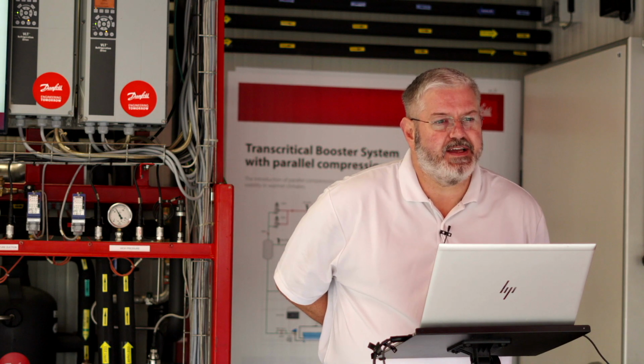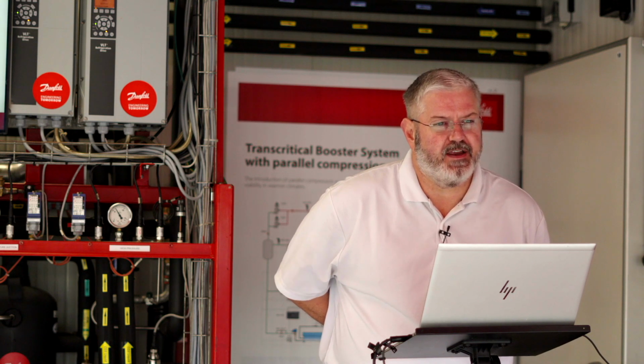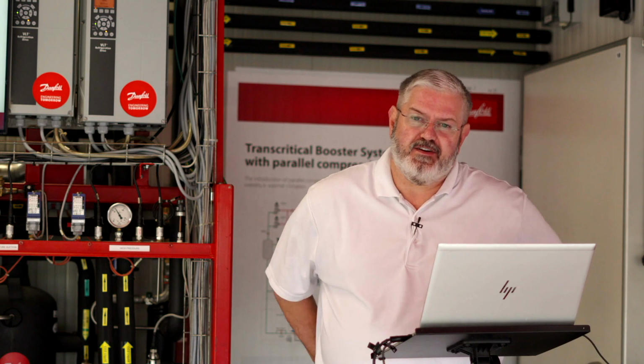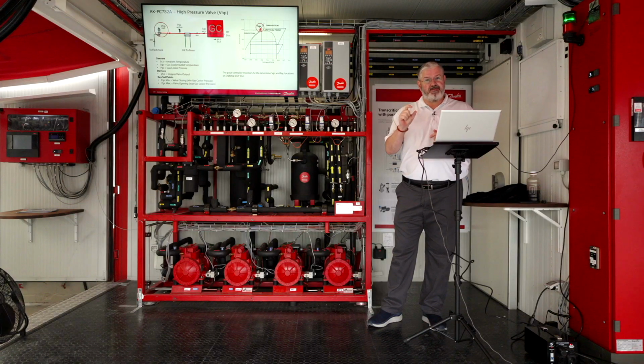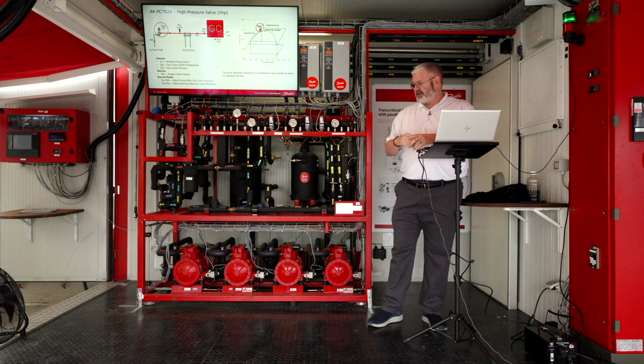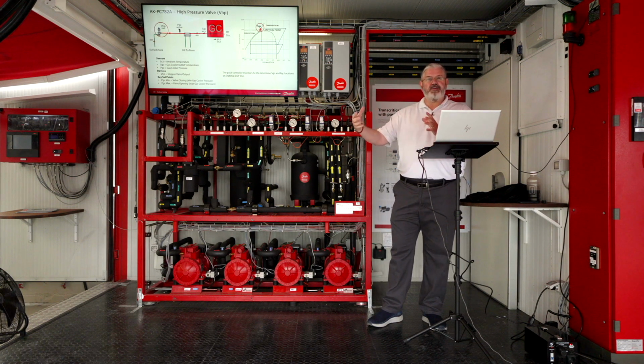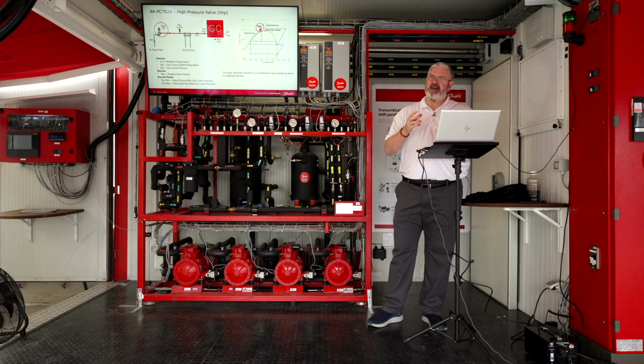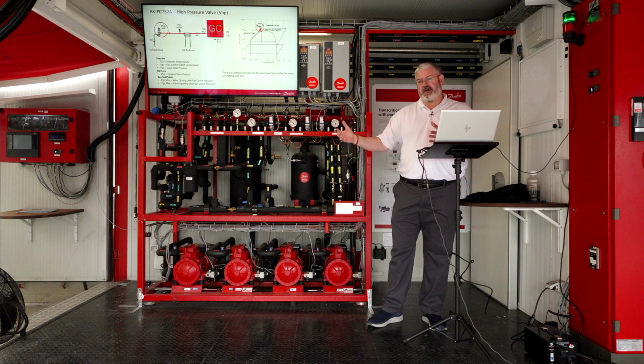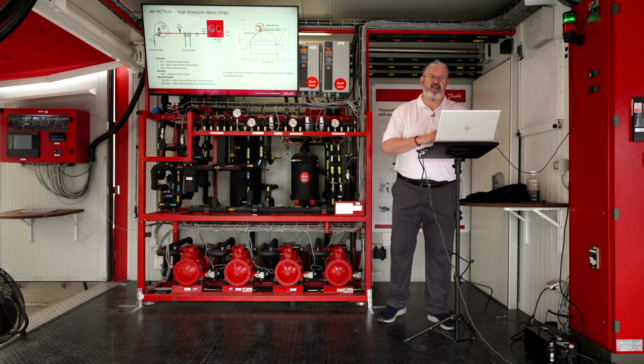So we have a question that says, are sites using CO2 keeping additional refrigerant on site? Yes, they are. It's asking about quantities. One thing I wasn't aware of till recently is that the cylinder providers, Airgas and such, do charge a storage fee for you having their cylinder over long periods of time. Especially people that are new with CO2, it's new, it's different, it must be spooky. They'll get an additional charge to keep it on site, like in perpetuity. But there is a cost to that. I don't know the dollar amount per cylinder. I think I heard the number of $30 or $40. But if you multiply that times 15 cylinders times 3 systems times 12 months, it's not financially viable to keep them around long term like that.